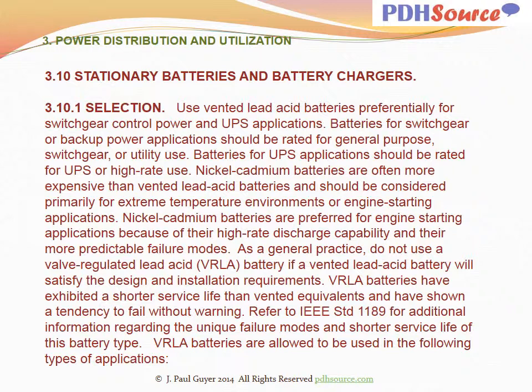more predictable failure modes. As a general practice, do not use a valve-regulated lead-acid battery if a vented lead-acid battery will satisfy the design and installation requirements. VRLA batteries have exhibited a shorter service life than vented equivalents and have shown a tendency to fail without warning. Refer to IEEE Standard 1189 for additional information regarding the unique failure modes and shorter service life of this battery type. VRLA batteries are allowed to be used in the following types of applications.